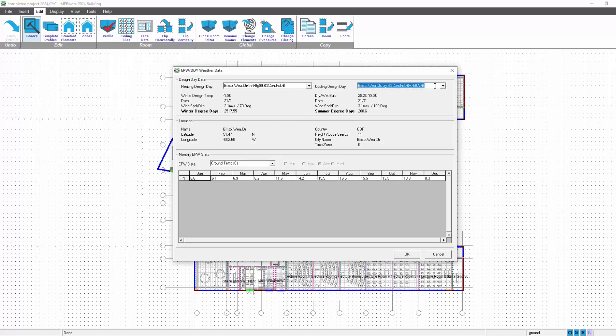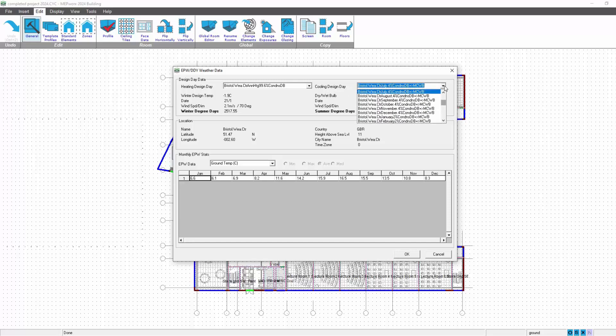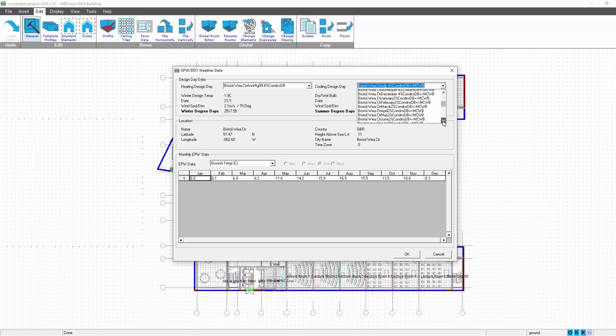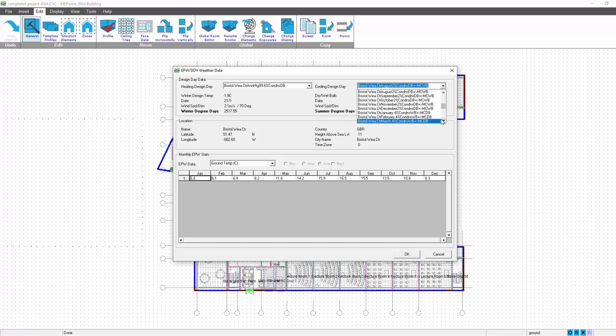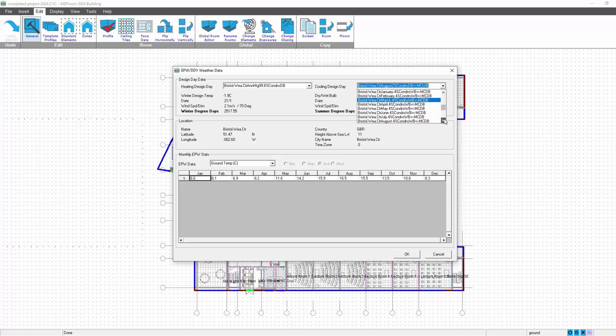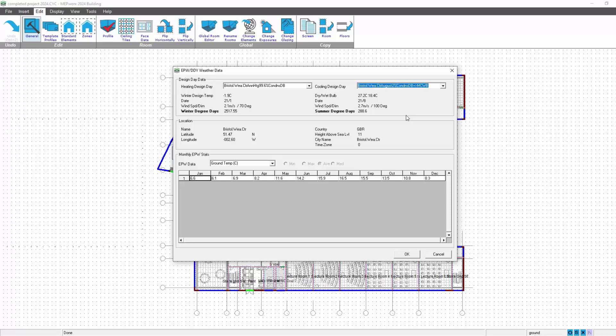Data set in the list doesn't necessarily reflect the highest temperature. The first one we've loaded is 28.2, but if we looked at another weather data set, for example, if I was to select August, that's 27, slightly less. So it's always worth reviewing the weather data sets to see what's happening. If you're doing cooling, likely it's not June, July, August. If I select July, it's 24.